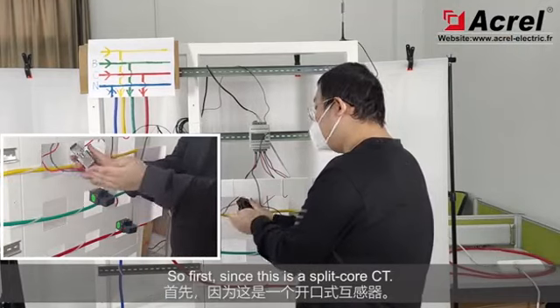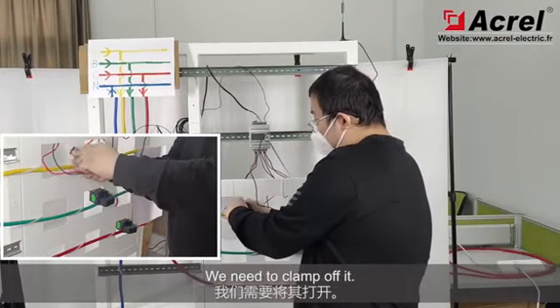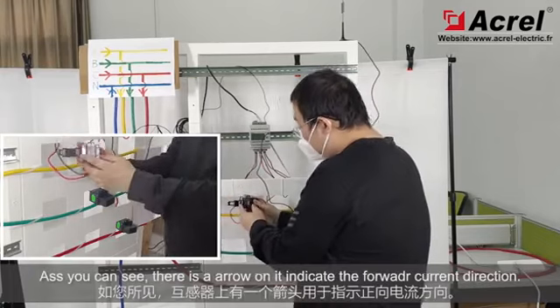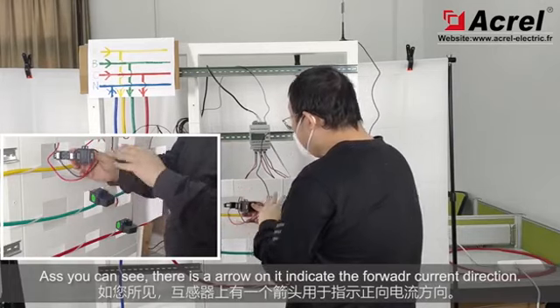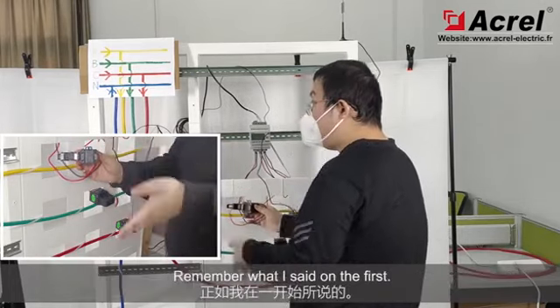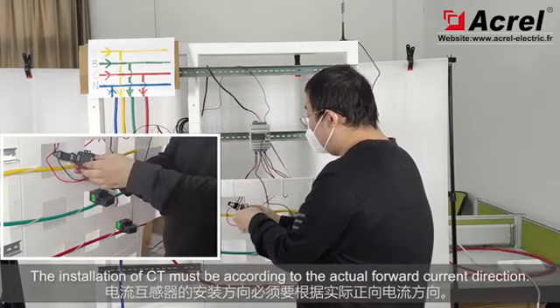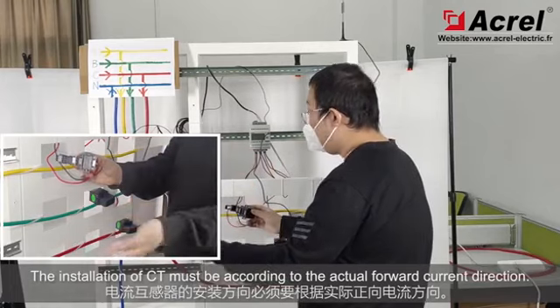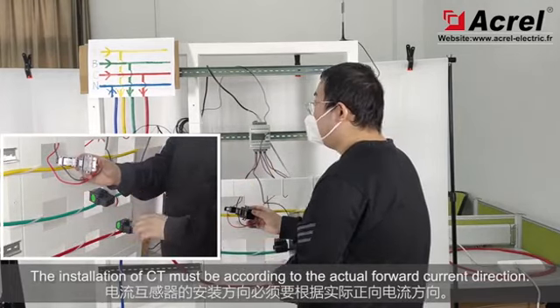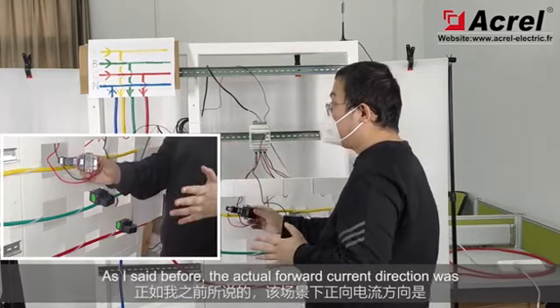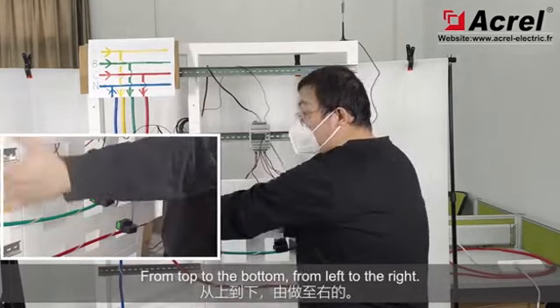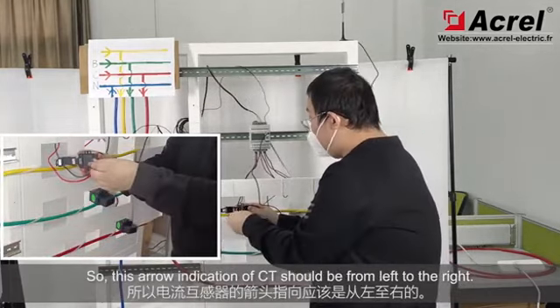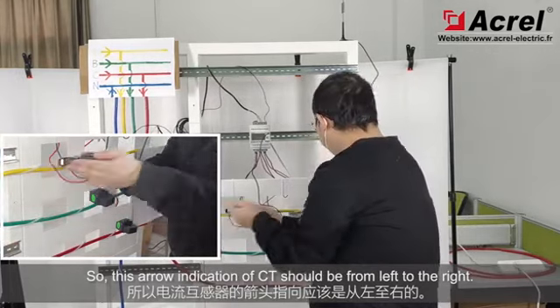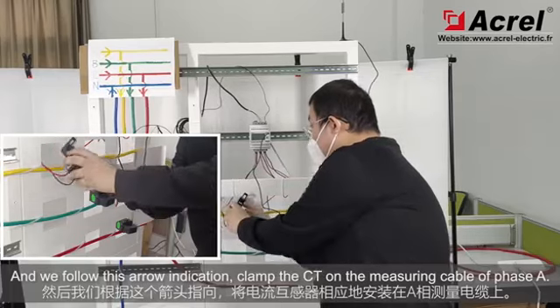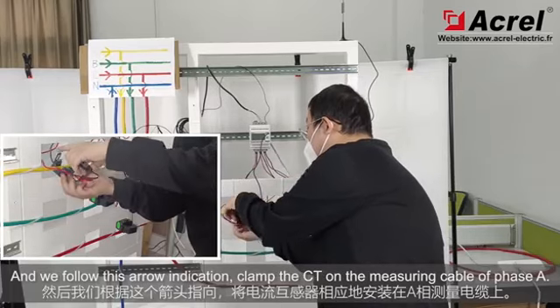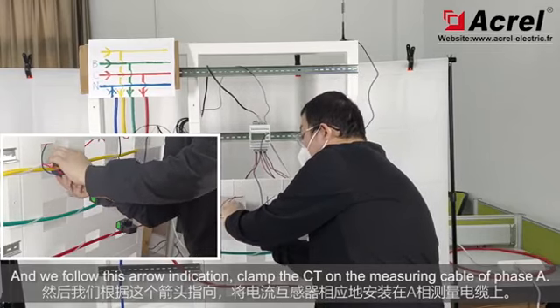So first, since this is a split core CT, we need to clamp it off. And as you can see, there is an arrow indicating the forward current direction. Remember what I said at the first. This installation must be according to the actual forward current direction. As I said before, the actual current forward direction was from top to the bottom, from left to the right. So this arrow indication should be from left to the right. And we follow this indication, clamp this CT on the measuring cable of phase A.